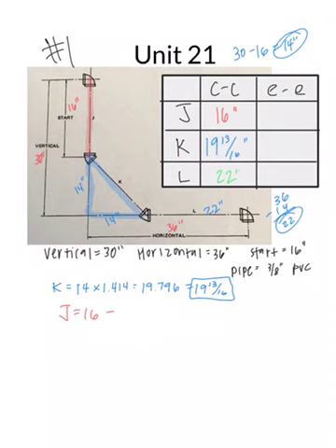So the 90 has a 3/8 takeoff. The 45 has a 1/4 inch takeoff. And finally, we don't have to add back the threads because this is PVC. So I'm going 16, take off 3/8, take off 1/4, and I get 15 and 3/8. So pipe J from end to end should be cut at 15 3/8.